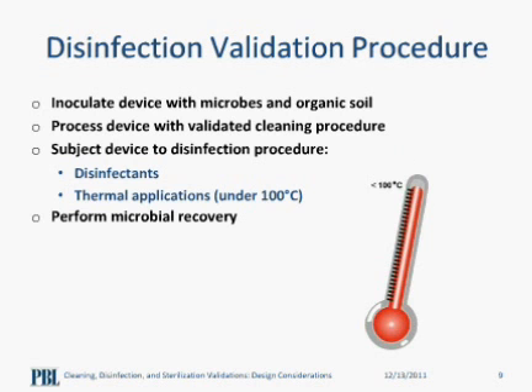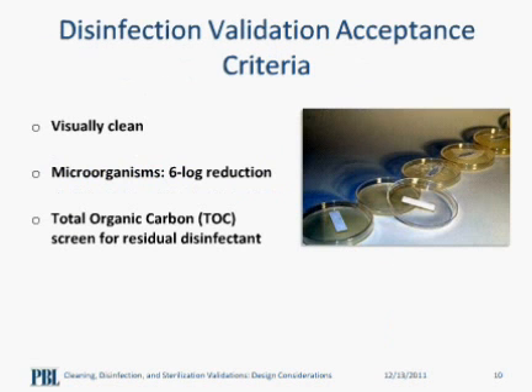Afterwards, we recover and enumerate any microbes remaining on the device. Based on the microbial recovery, we can compare the positive controls with the cleaned devices to determine if a 6-log reduction of microbes is achieved. If the device is both visually clean and satisfies the 6-log reduction, the disinfection procedure would be validated. As a side note, according to the AAMI guidelines, you may want to consider screening for harmful residuals remaining from your disinfectant and its potential risk to the patient. Obviously, if you apply thermal applications, a screening would not be necessary. As you can see, in disinfection only a 6-log reduction of microbes is required, but some devices are required to be sterile.